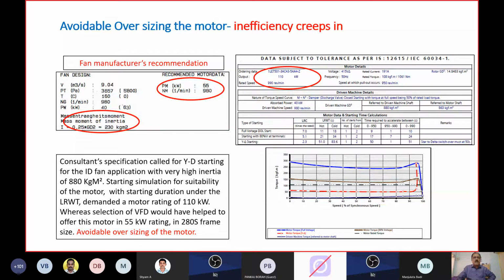Sure, sir. So as you can take a look here, a 55 kilowatt motor, because of the high inertia and star delta starting, which is called restricted starting, requires a selection of a 110 kilowatt motor. The moment you choose a motor which is almost double the size of the BKW of the fan, the efficiency goes for a toss. So we need to restrict selection of motors. The ideal choice here would be to select a DOL starting or a VFD starting, so that 55 kilowatt at best can be 75 kilowatt, not 110 kilowatt. So this is just one slide, a commentary on how inefficiency creeps in when you select a motor based on the consultant specification.